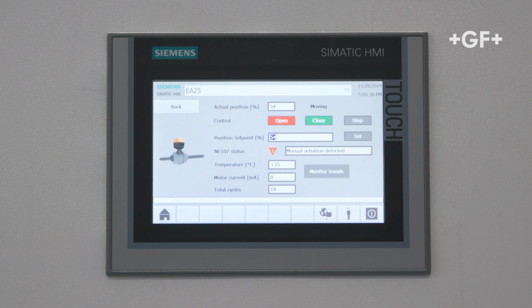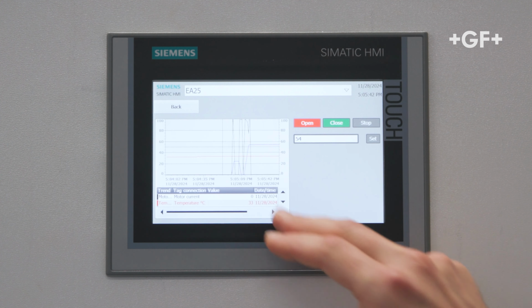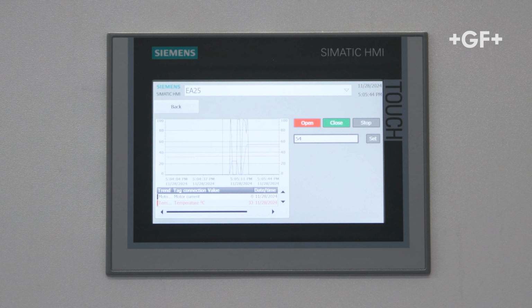There's a lot of additional data available that can be transmitted from the device to the PLC. In this example, we can see the temperature, the motor current, and even the total cycles of the electric actuator over its lifetime. This data can be monitored over a certain time period, and by this you can easily see if there's any abnormality of the motor current, for example, which means there is probably an issue with the connected valve.